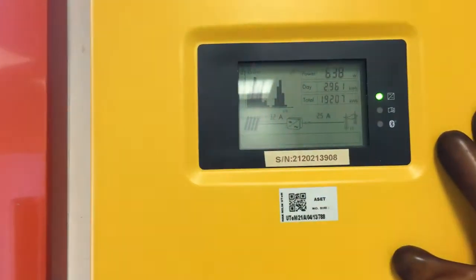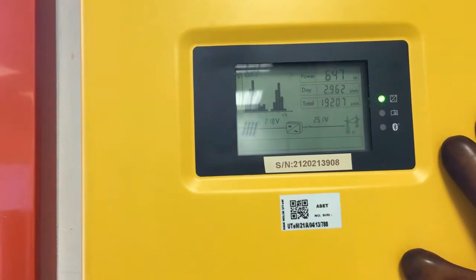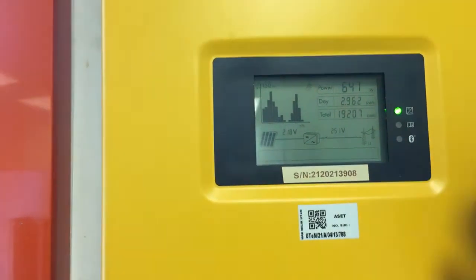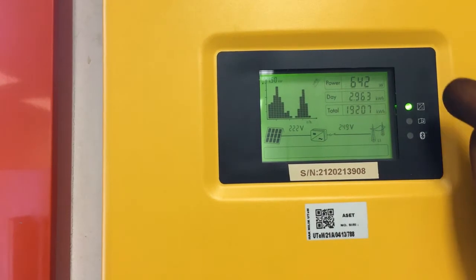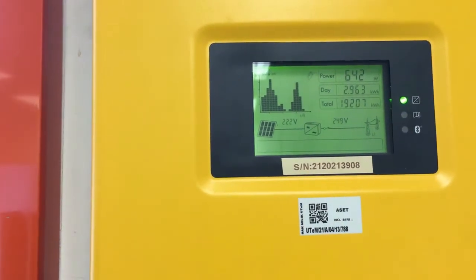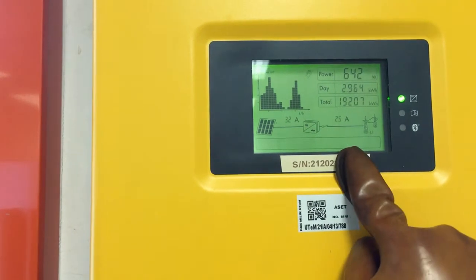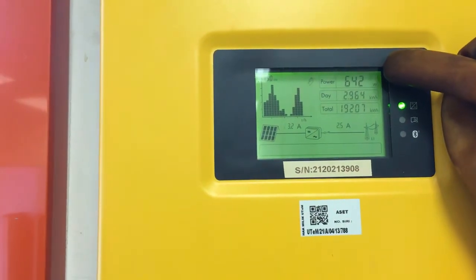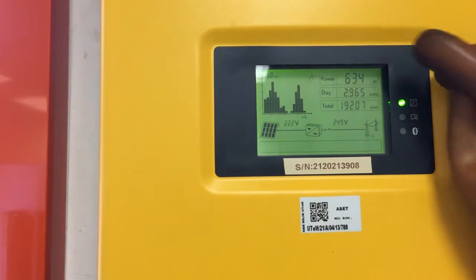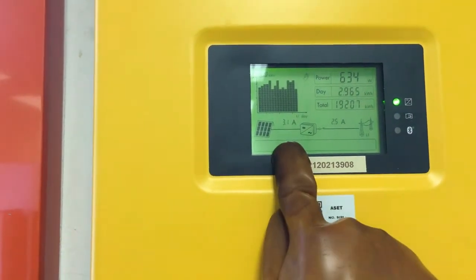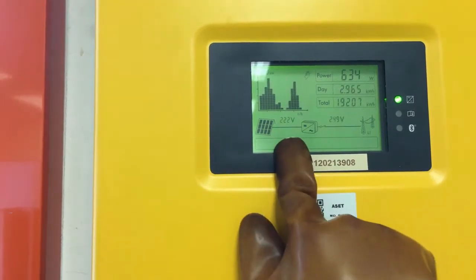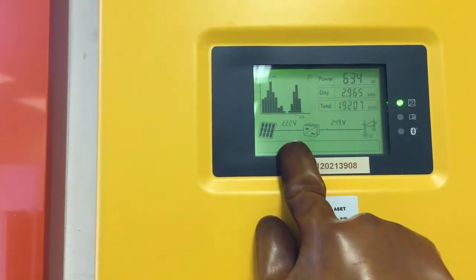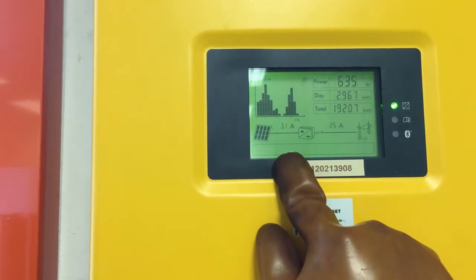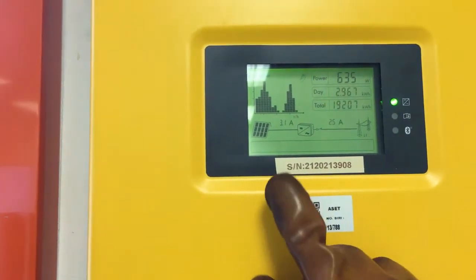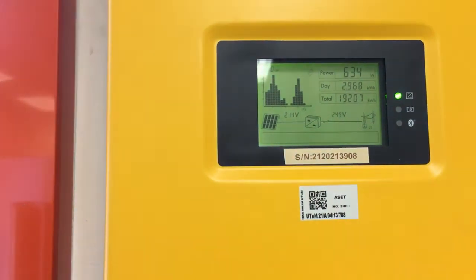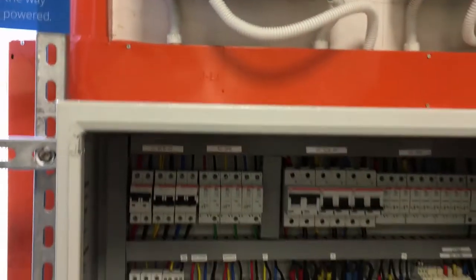Okay, so for PV, one of the ways that they design the inverter is that when you tap, the indicator light will turn on and you can see better. So this is the DC side, this is the AC side, and this is the current instantaneous power that is produced now. Right? So if I tap again, then it's going to change from current. I tap again, I can get the voltage. So this is the standardized design for inverters on site, for you to be able to read them easily. Okay, so this is how you turn on the system for the first time.